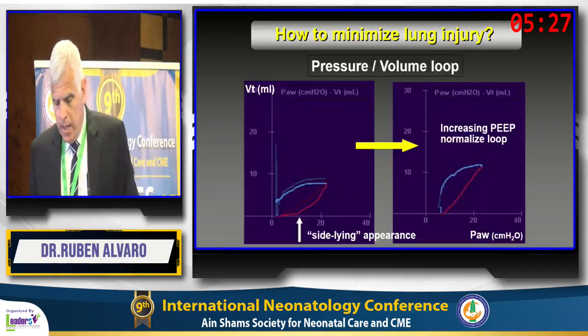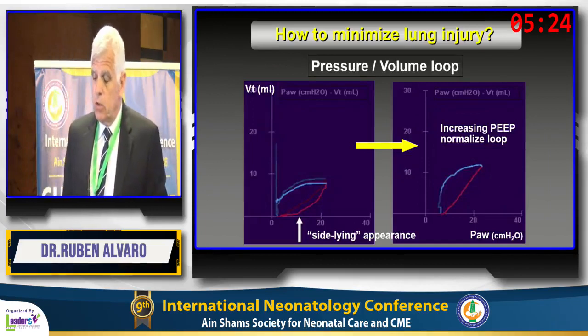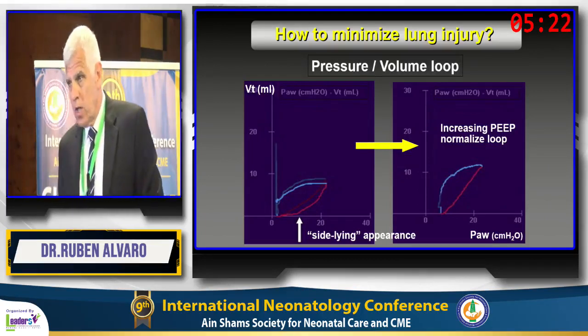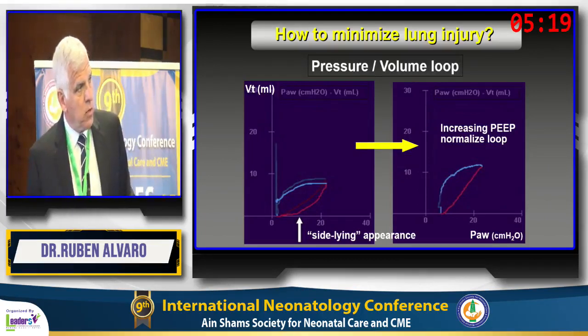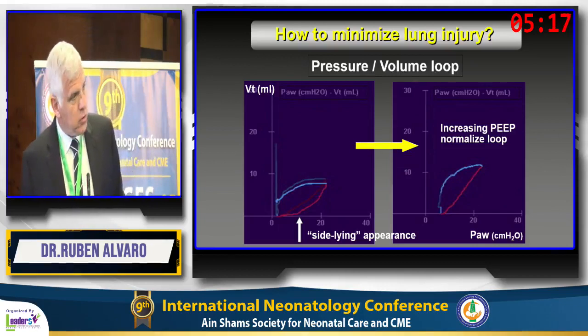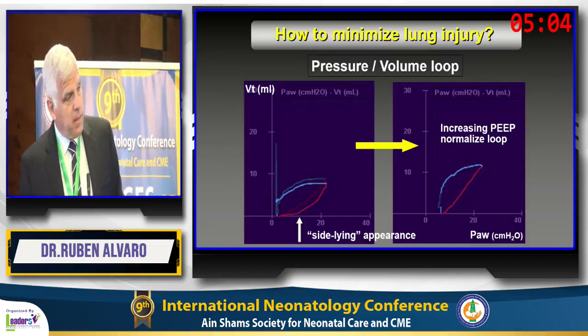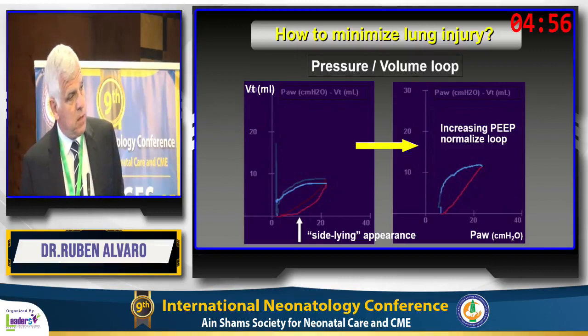So how do we know your PEEP is adequate? We look at the volume pressure curve. As you can see here, the inspiration in red starts flat at the beginning, meaning you need a lot of pressure before any air gets into the lungs. That's because your PEEP is too low here. This is the opening pressure for these lungs, so you should start your curve right from here. You do that by increasing the PEEP.